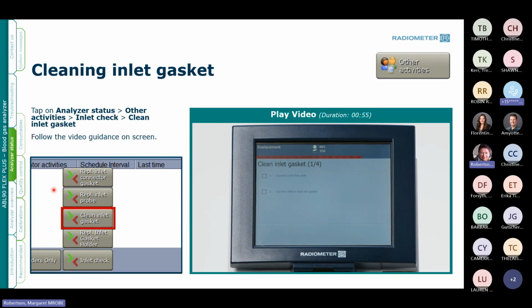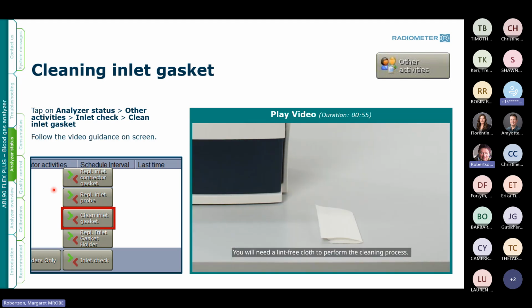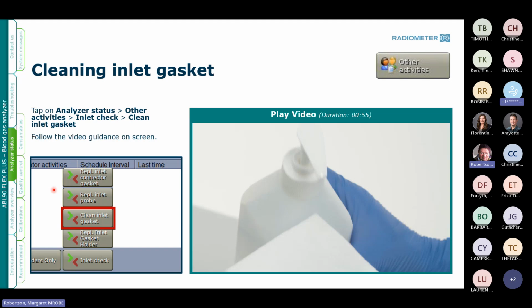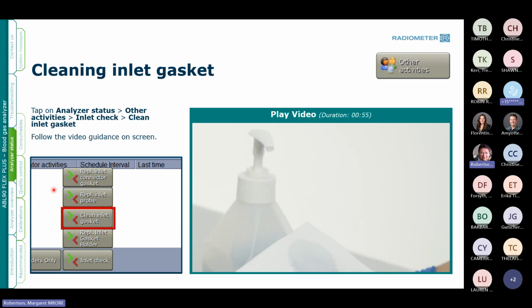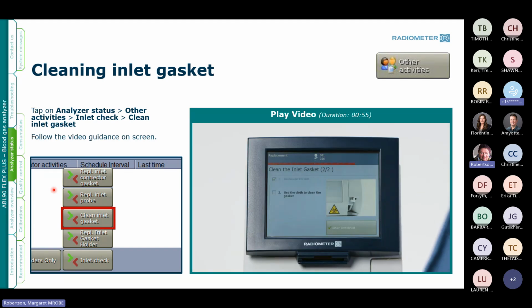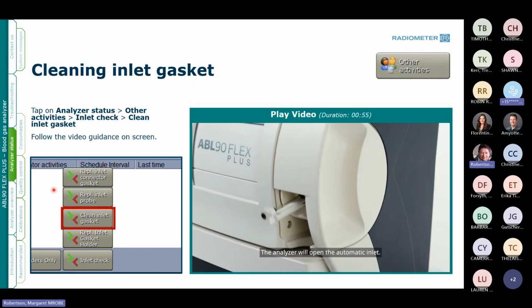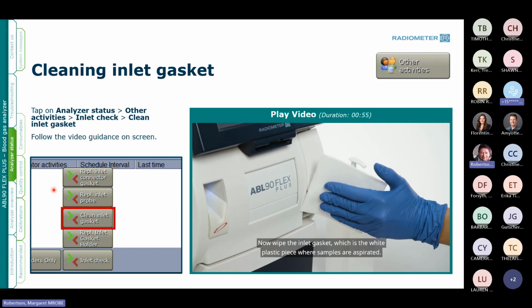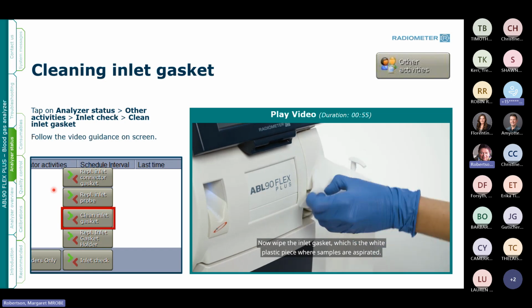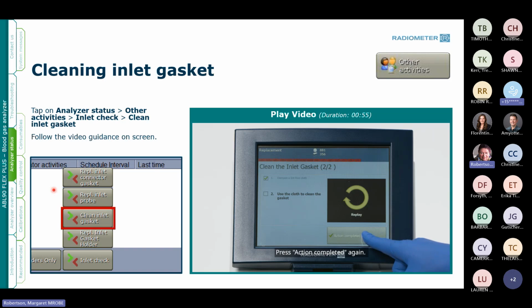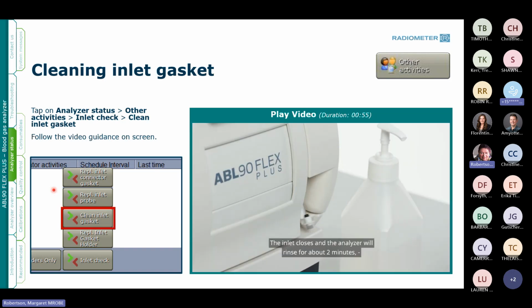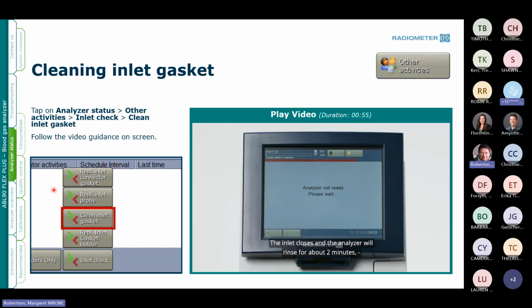Follow the instructions. You will need a lint-free cloth to perform the cleaning process. Dampen the cloth with tap water. Then press Action Completed. The analyzer will open the automatic inlet. View the probe first to make sure it is not bent. If bent, it would need replacement instead of cleaning. Now wipe the inlet gasket, which is the white plastic piece where samples are aspirated. Press Action Completed again. The inlet closes and the analyzer will rinse for about 2 minutes. Then go to Ready.